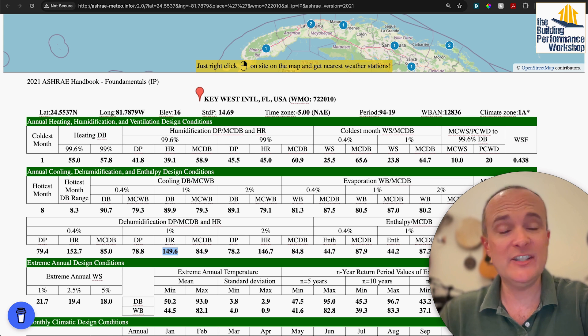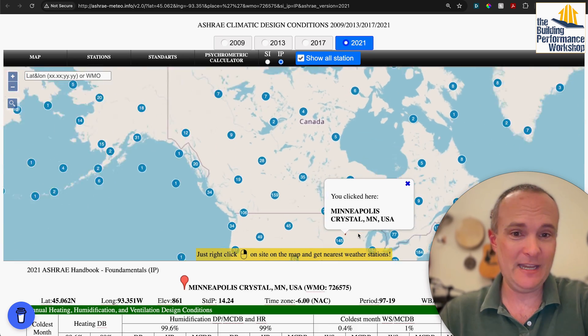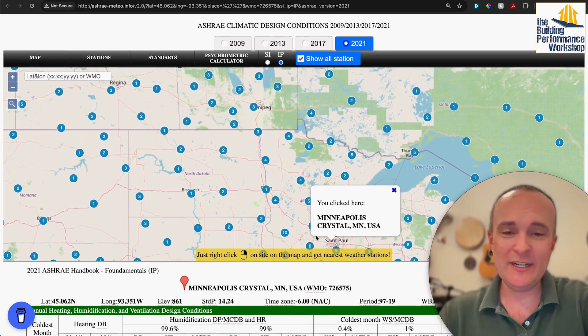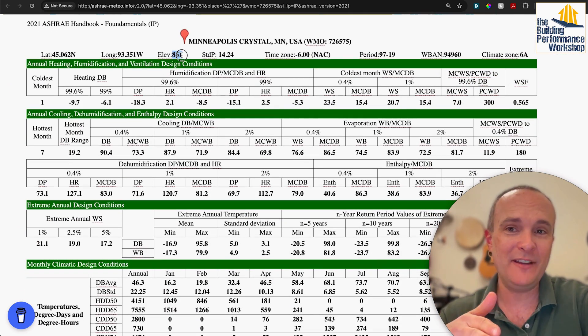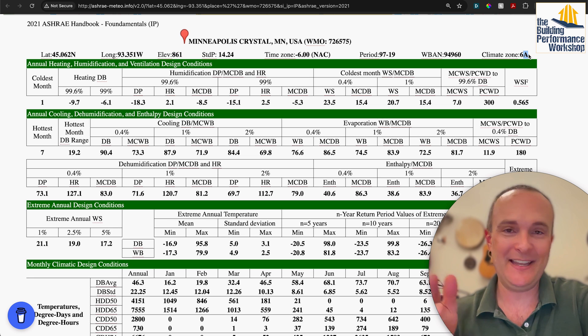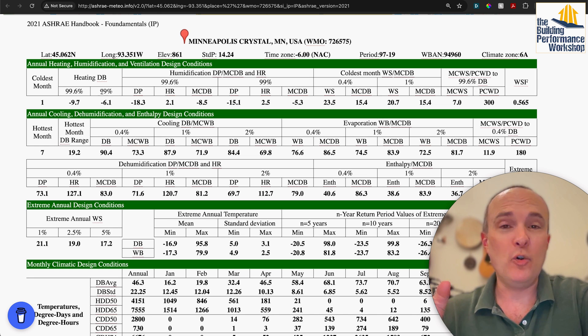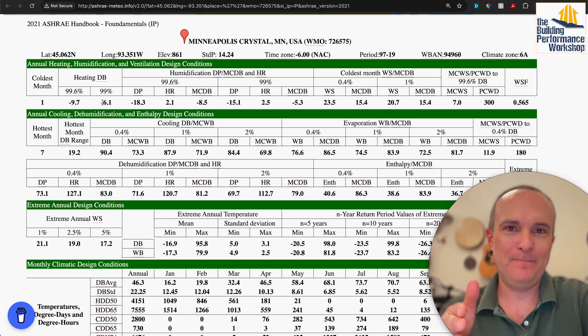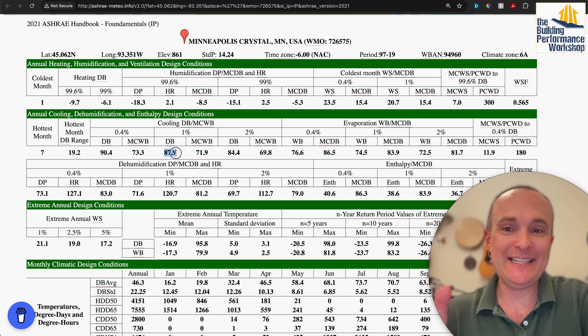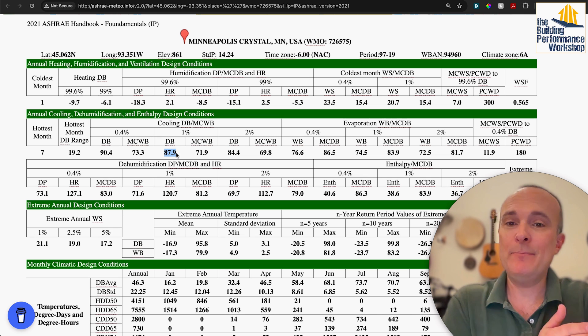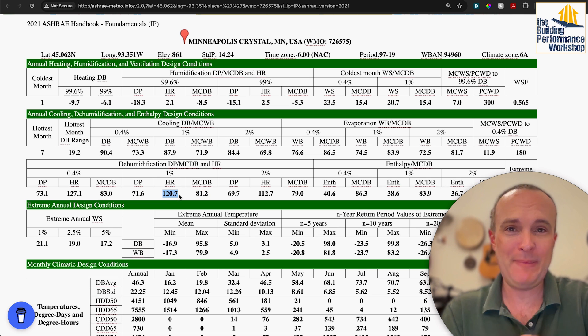Now let's go to a place you would not associate with being really wet: Minneapolis, Minnesota. Minneapolis has cold winters — we're at just under 1,000 feet of elevation, in climate zone 6a, about as cold as it gets in the continental U.S. Our 99% coldest temperature is negative 6 Fahrenheit. Our 99% hottest is 88 degrees, but our 99% wettest temperature is 81, and we still have 121 grains per pound of moisture in the air.